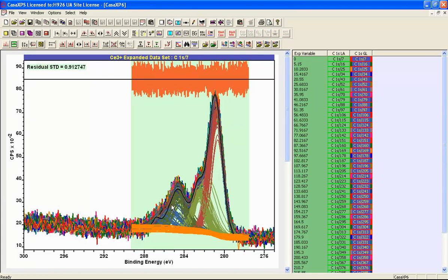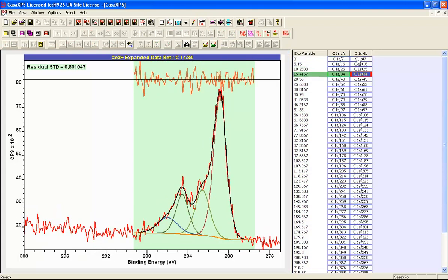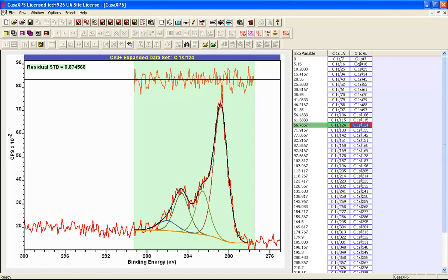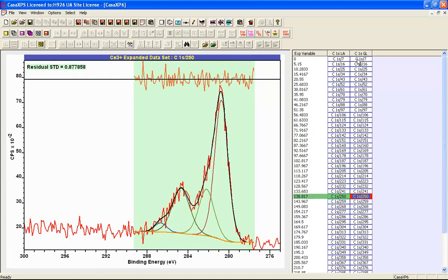in these peaks, and the reliability of a peak model based on the GL line shape fitted to these data is nowhere near as consistent as you obtain when you have a line shape that is based on a Voigt function. And this is the primary reason why the LA line shape is preferred to a GL line shape.